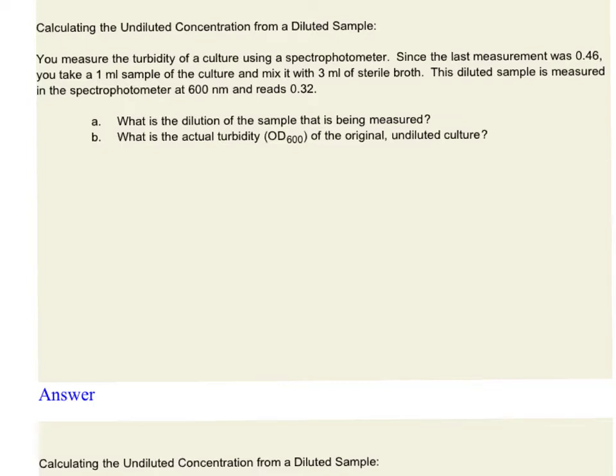When using a spectrophotometer, turbidities are not accurate above a reading of 0.5. Since the last measurement was 0.46, it's necessary to dilute the sample prior to taking the measurement.